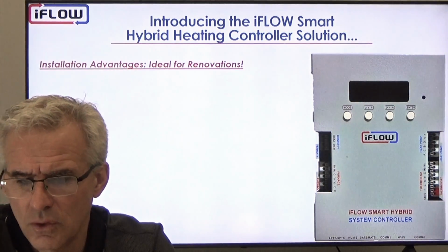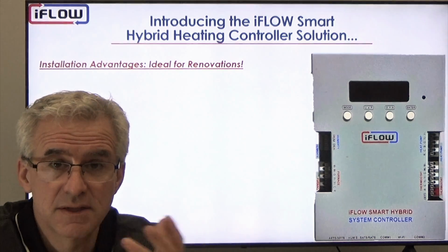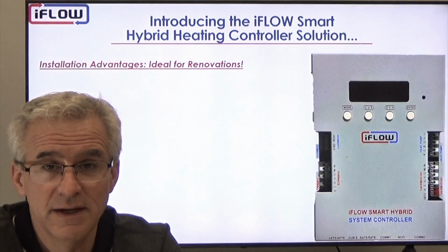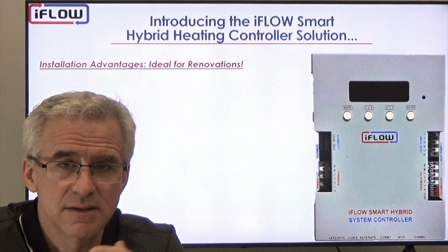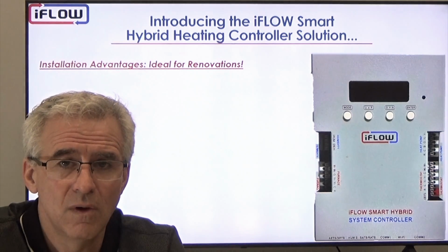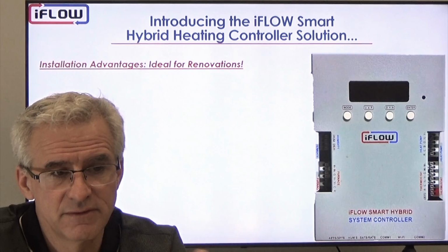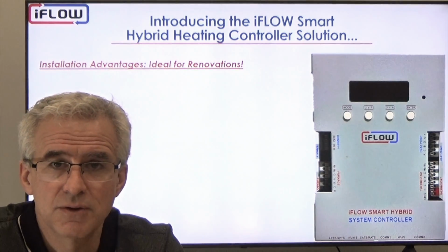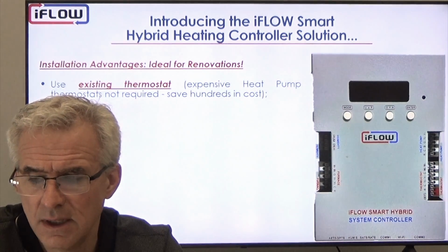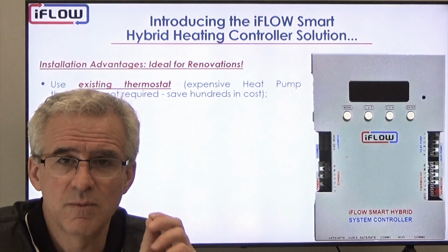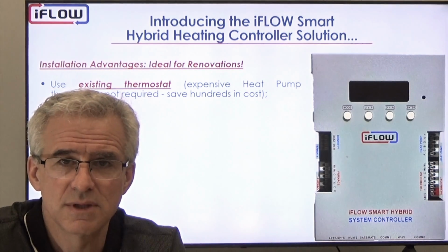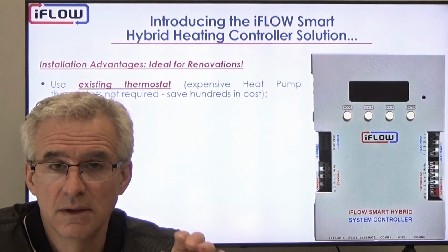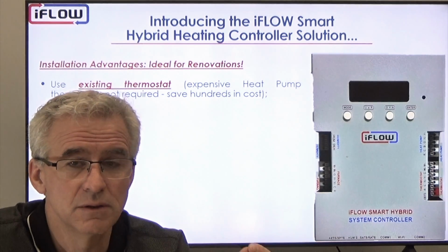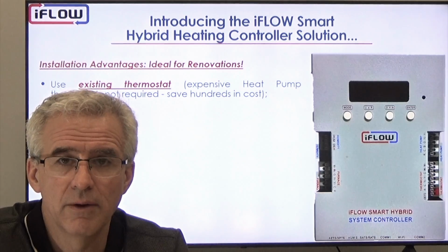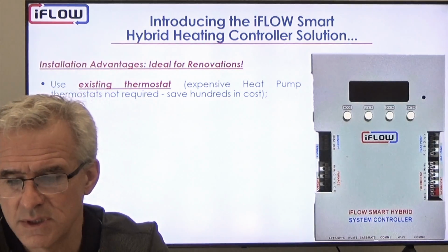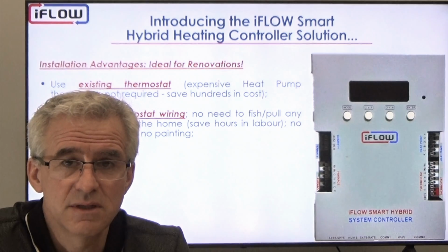So, our controller's installation advantages: they're ideal for renovations. As I mentioned, in that scenario where you only have 4 wires in the wall, instead of spending hours trying to fish new wire down for that, we can use the exact same thermostat. You don't need to change the thermostat. You don't need a heat pump thermostat. So again, we can save a couple hundred dollars there at least by not requiring you to upgrade to a heat pump thermostat. We can use the existing wiring.